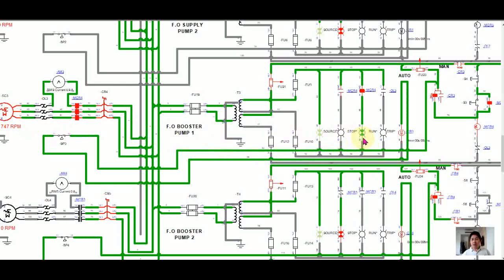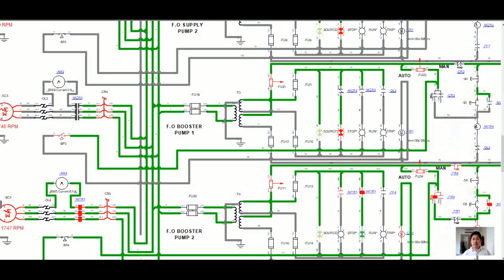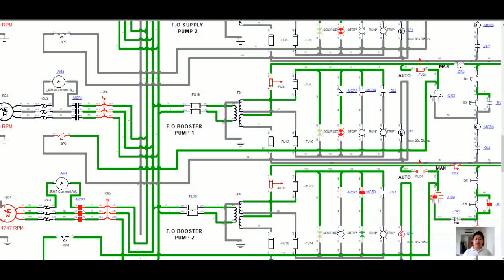I want to simulate the standby system. In case of low fuel oil pressure of booster pump number one, I will remove the fuel oil supply pressure, and your fuel oil booster pump number two automatically starts running. You can then switch off your number one fuel oil booster pump. Now fuel oil booster pump number two is running.